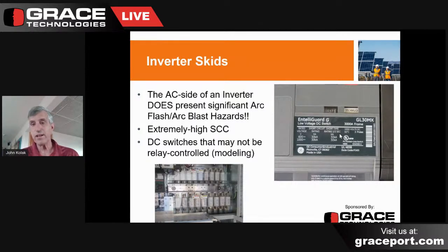And in an incident energy calculation, it would have no value at all. It's essentially a bus bar as far as we're concerned from the arc flash standpoint. So on this, you do encounter this on solar farms where you may have a three-phase breaker used as individual phases, or you could have three single-phase breakers used on this side of the system. So it's a rather unique piece of equipment from a training aspect. And from an arc flash standpoint, we ignore any DC switches or AC switches that aren't controlled by relays. They have no impact on incident energy at all.